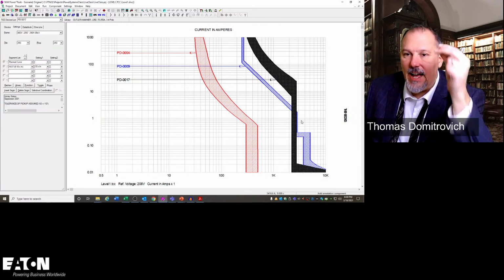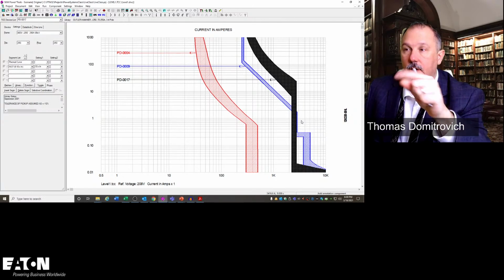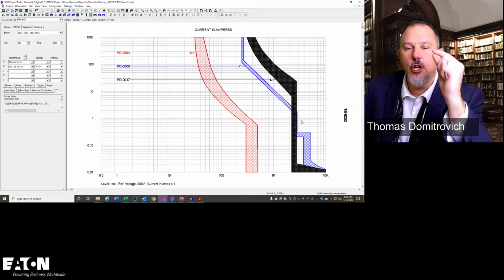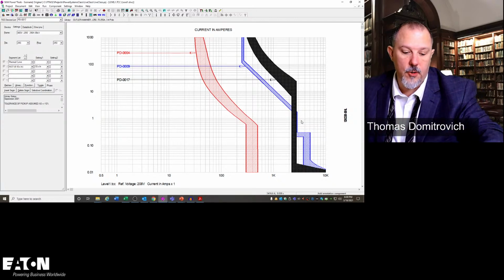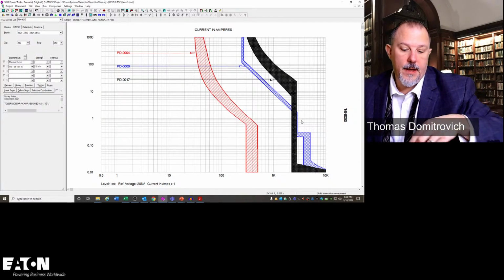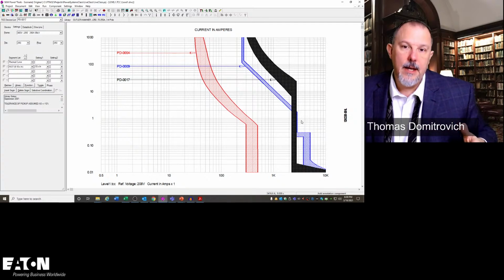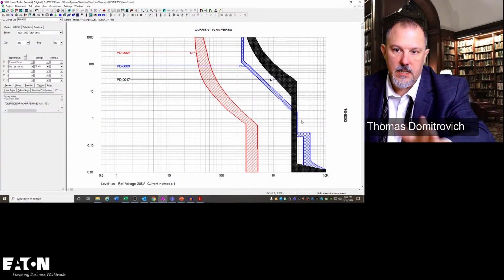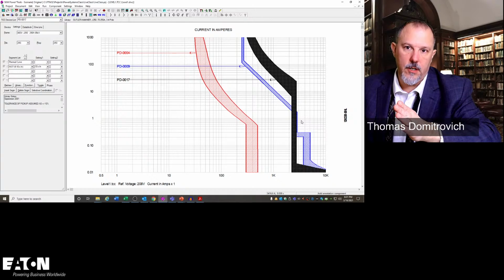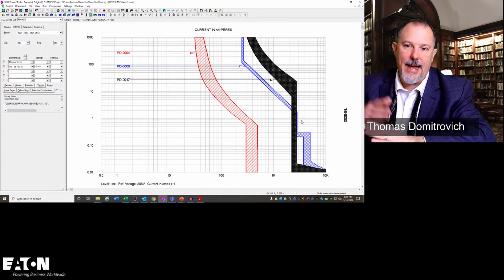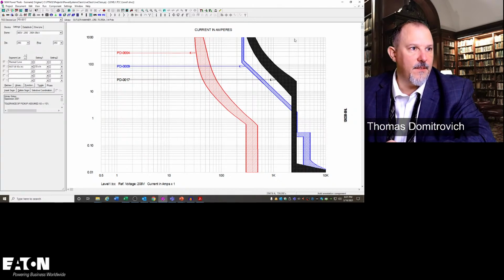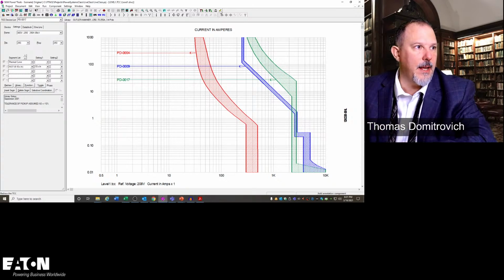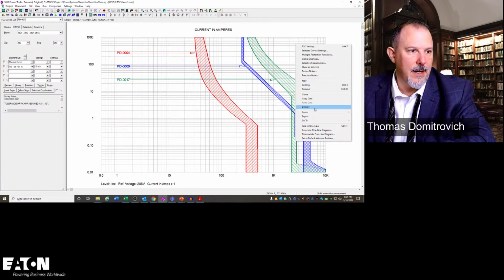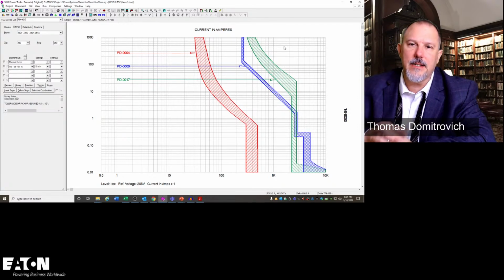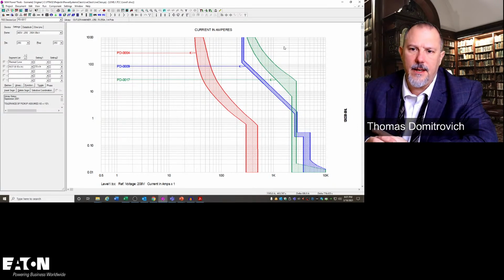I have to plot my bolted fault current value on here. Now, you may say, look, it's not a code requirement. And this is what I used to do. If I had a commercial or an industrial facility that wanted me to do a coordination study, I would plot the curves like this. I would plot my bolted fault current, and I would put a little flag on my TCC curve. If I was good at this, I could probably do it manually here, but I'm not going to because I can't remember how to do it. In any case, I'm not going to waste your time learning how to use SKM.